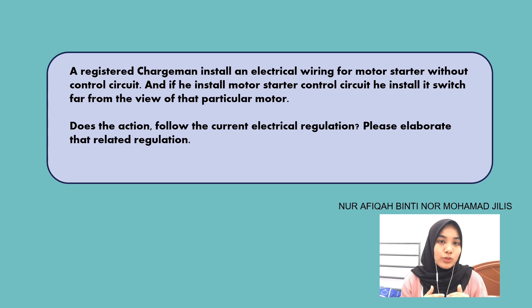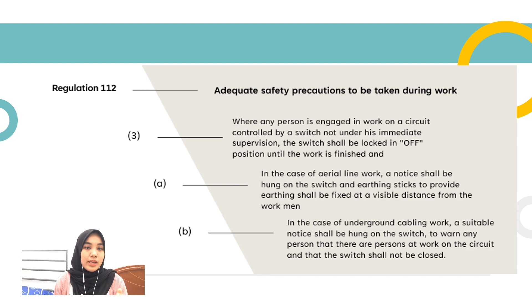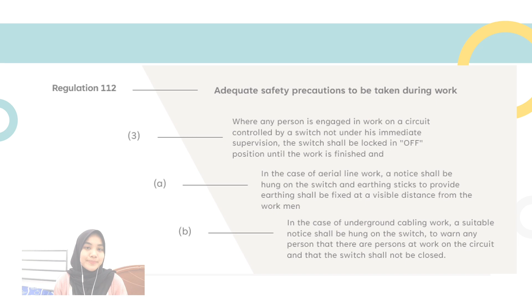Following that, I choose Regulation 112, on adequate safety precautions to be taken during work, under Maintenance of Installation. Sub-regulation 3 states where any person is engaged in work on a circuit controlled by a switch not under his immediate supervision, the switch shall be locked in the off position until the work is finished. In the case of aerial line work, a notice shall be hung on the switch and an earthing stick to provide earthing shall be fixed at a visible distance from the workman. And in the case of underground cabling work, a suitable notice shall be hung on the switch to warn any person that there are persons at work on the circuit and that the switch shall not be closed.